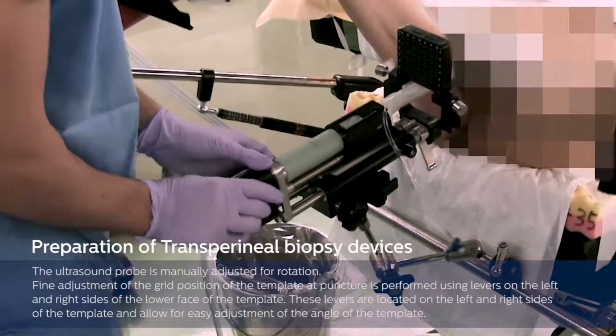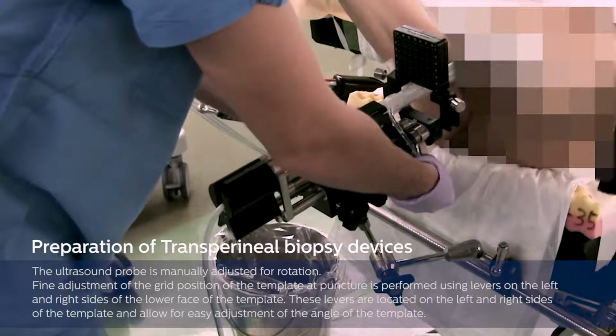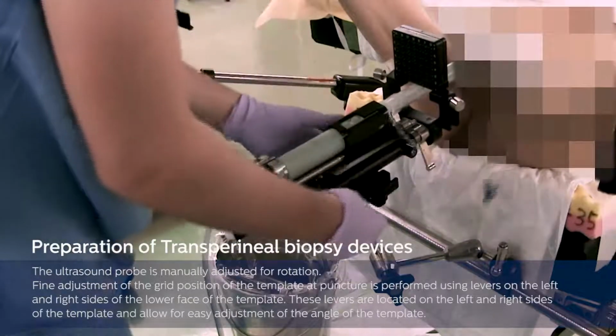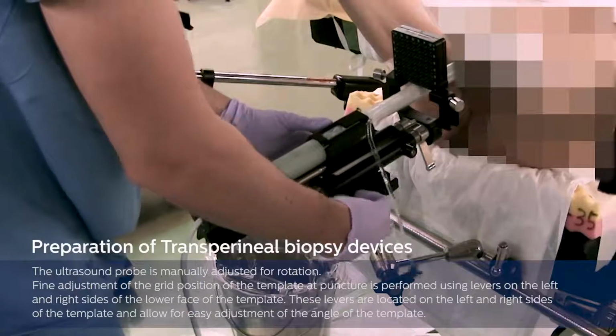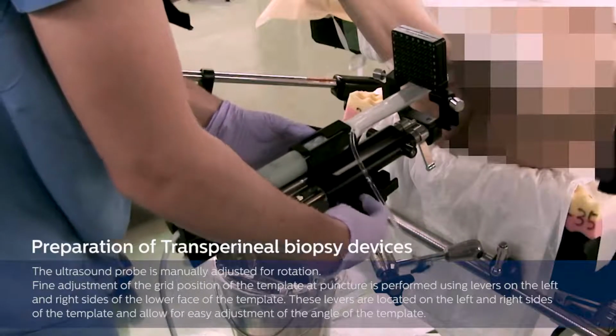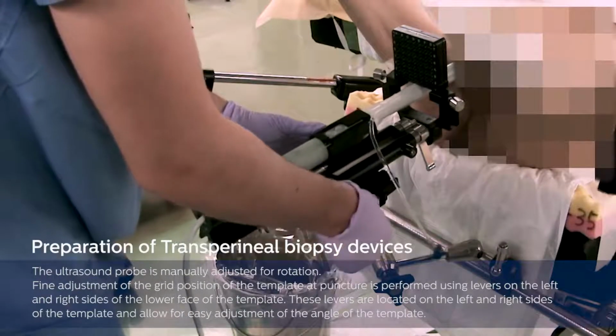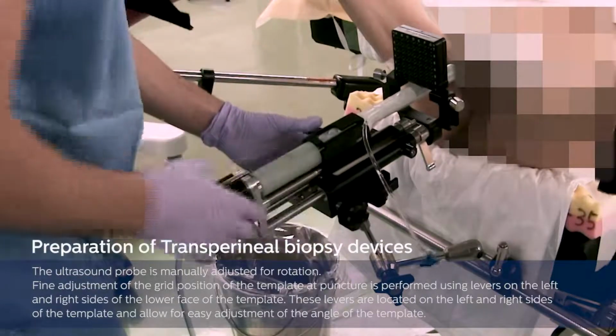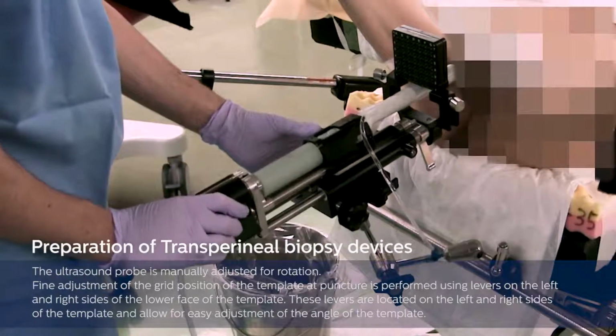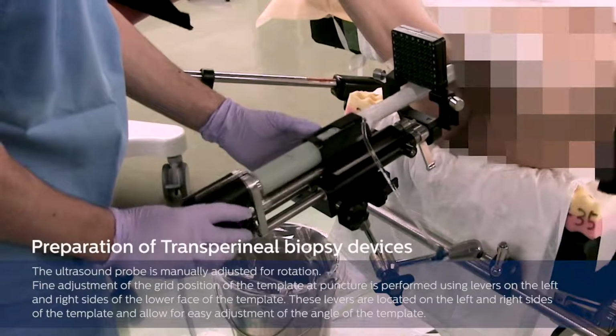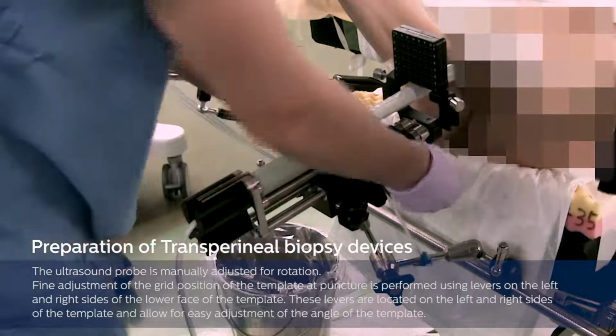The ultrasound probe is manually adjusted for rotation. Fine adjustment of the grid position of the template at puncture is performed using levers on the left and right sides of the lower face of the template. These levers are located on the left and right sides of the template and allow for easy adjustment of the angle of the template.